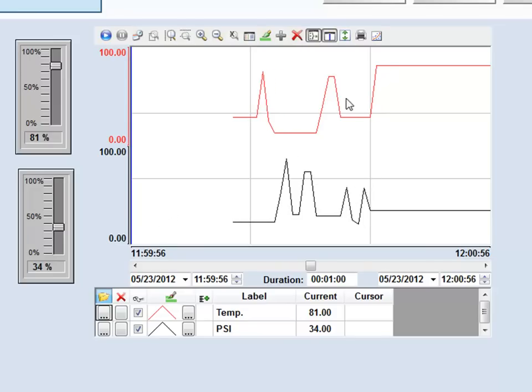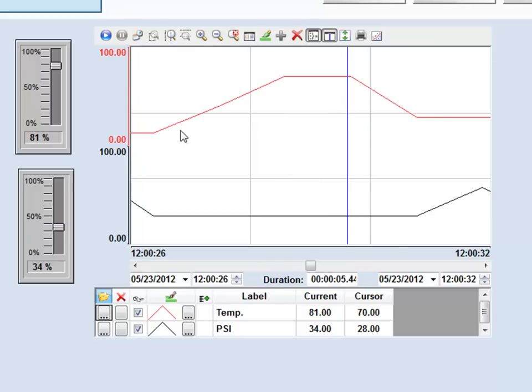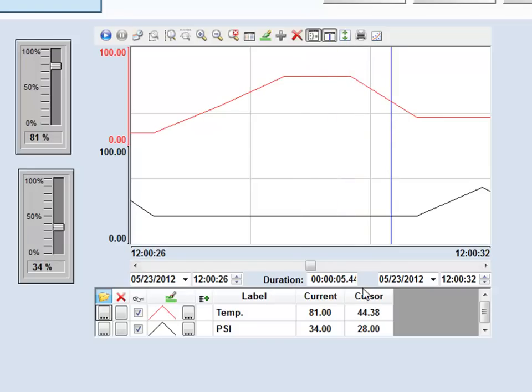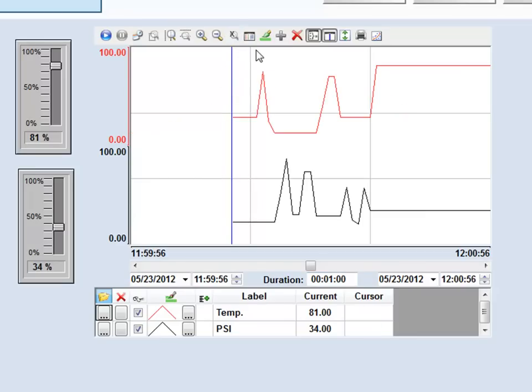I can pause and examine a peak. Using the horizontal zoom tools, I can select a starting and end point and zoom in on that individual area. I also have this blue cursor line enabled via the icon on the toolbar. I can move the cursor around and it will show me the value where the cursor crosses the trend line. In another part of the video I'll show where that cursor value can also be sent out to a tag.